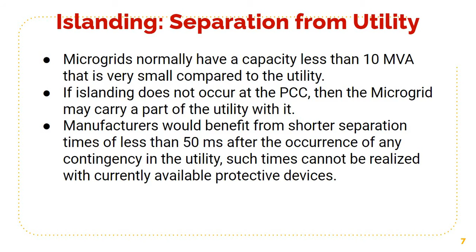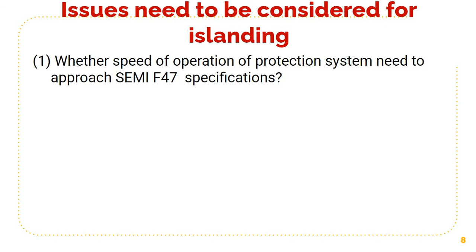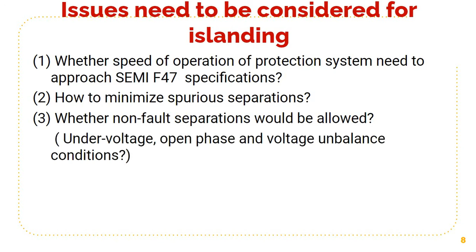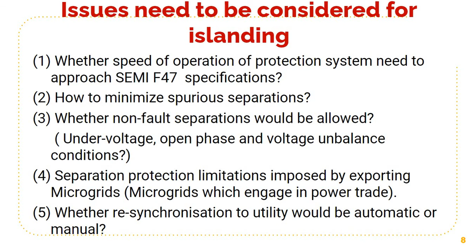First one is whether speed of operation of protection system needs to approach the SEMI F47 specification. We will see it in the next slide. Second, how to minimize spurious separations; third, whether non-fault separations would be allowed; and fourthly, separation protection limitations imposed by exporting microgrids. Exporting microgrids means microgrids which engage in power trade, which are already selling energy, and finally whether resynchronization to utility should be done automatic or manual.